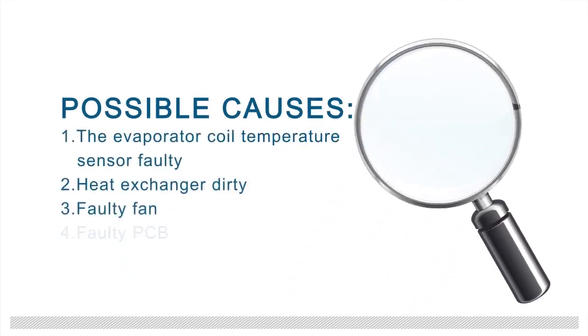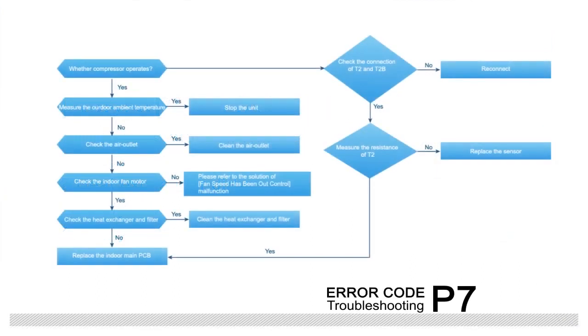The failure may be caused by evaporator coil temperature sensor faulty, heat exchanger being dirty, faulty fan, and faulty PCB. Troubleshooting is shown in figure.